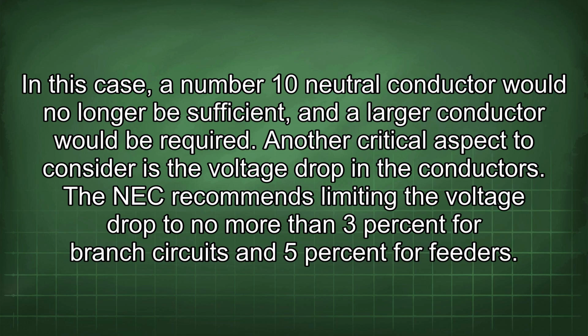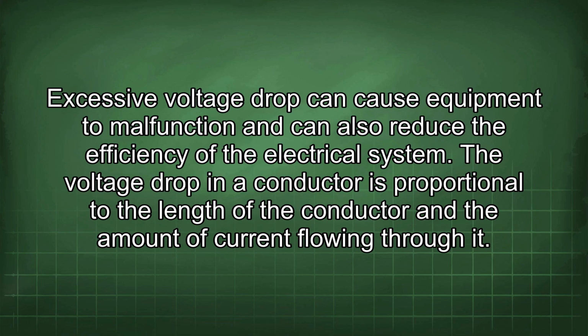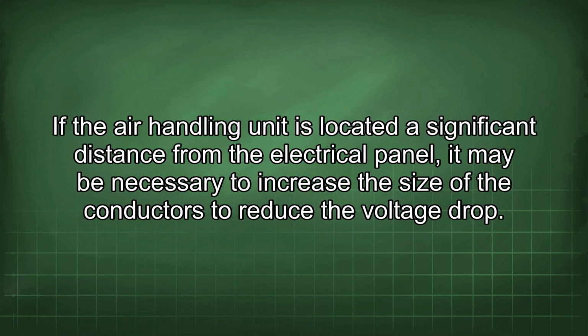Another critical aspect to consider is the voltage drop in the conductors. The NEC recommends limiting the voltage drop to no more than 3% for branch circuits and 5% for feeders. Excessive voltage drop can cause equipment to malfunction and can also reduce the efficiency of the electrical system. The voltage drop in a conductor is proportional to the length of the conductor and the amount of current flowing through it. If the air handling unit is located a significant distance from the electrical panel, it may be necessary to increase the size of the conductors to reduce the voltage drop.